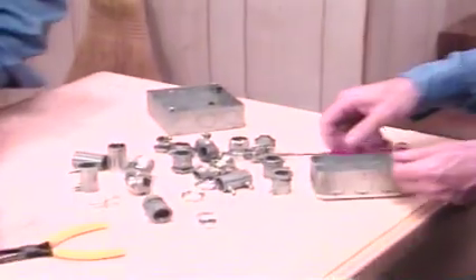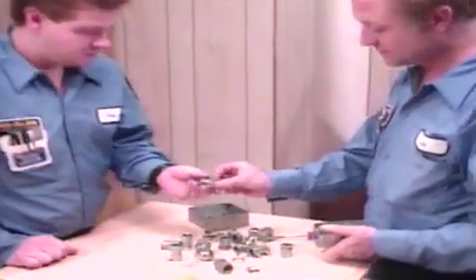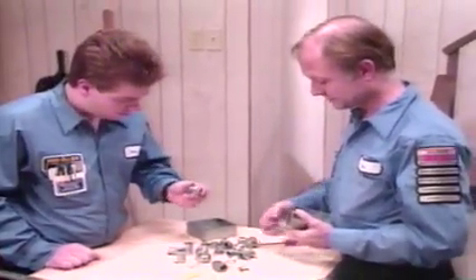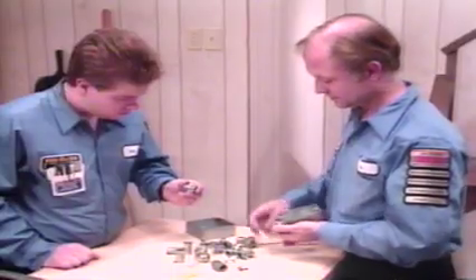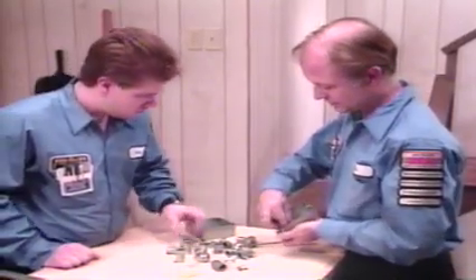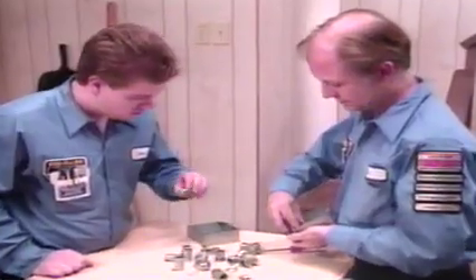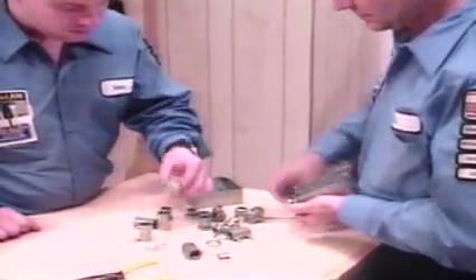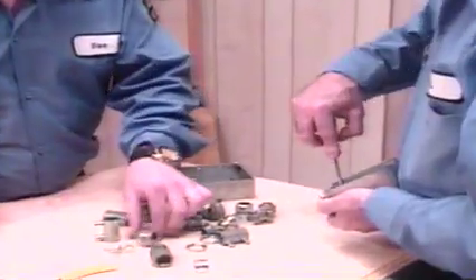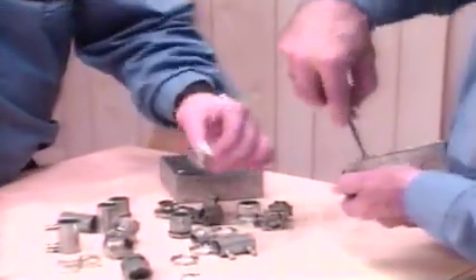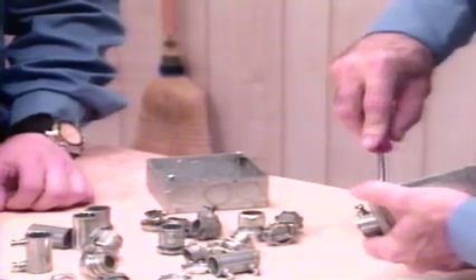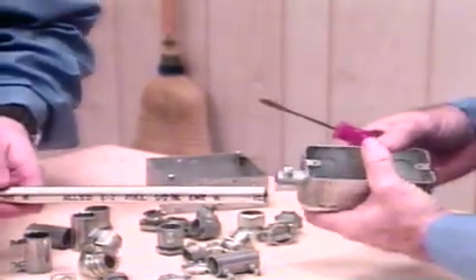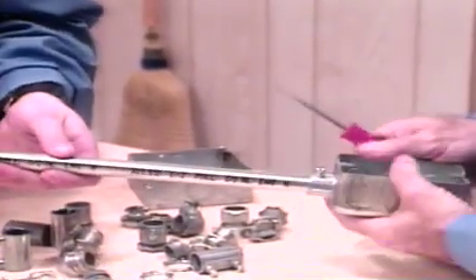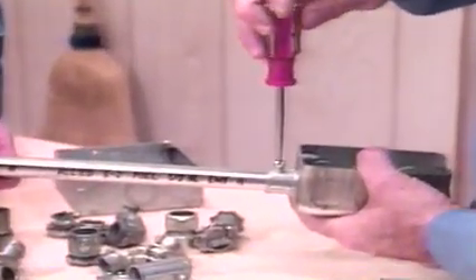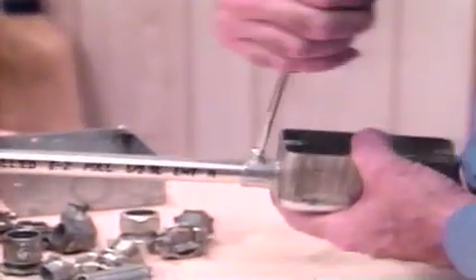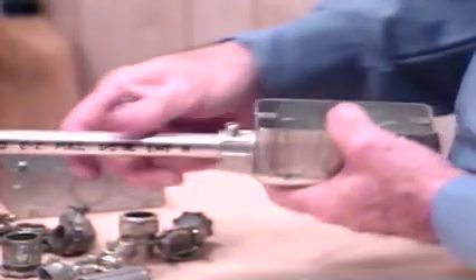Conduit requires the use of special connectors, couplings, brackets, and general hardware. This is a conduit set screw connector that you would use to attach the conduit to a metal box. All right, good, excellent. All right, now give me the conduit there. Make sure that once the conduit is attached to the box, you tighten the set screw down to keep the conduit from pulling away from the box. Just so it's nice and firm.